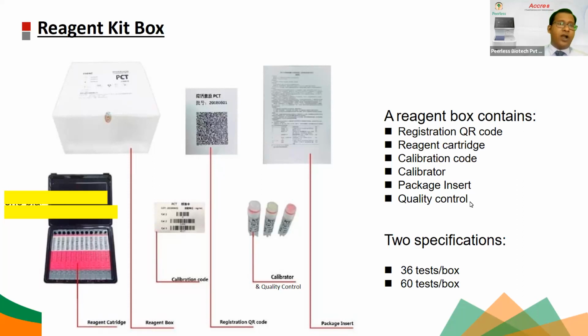Now you can ask me, you are already providing a calibration code, then why are you providing an extra calibrator? Actually, in ELISA or CLIA, you need to do a minimum 5 to 6 point calibration, correct? You all know that, and that should be done in duplicate, which will take around 6 to 12 tests in normal cases. But generally, people don't want to spend that much, because they have to form the calibration curve while they do the calibration. Sometimes it takes time, sometimes it is not so convenient.